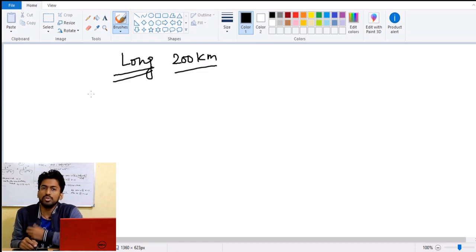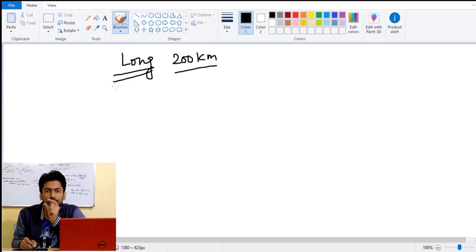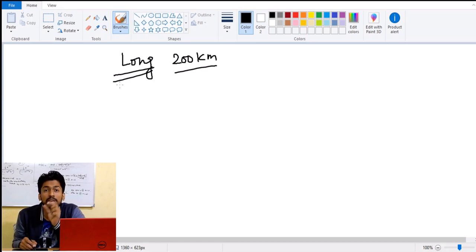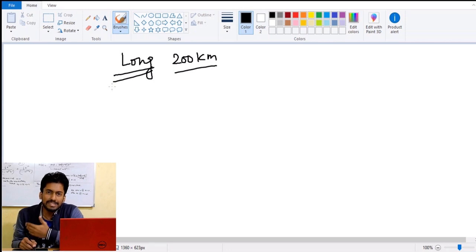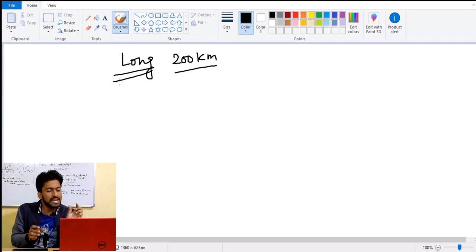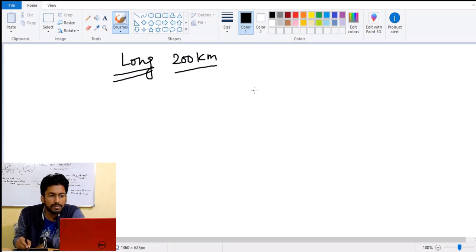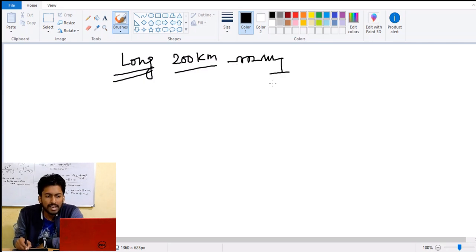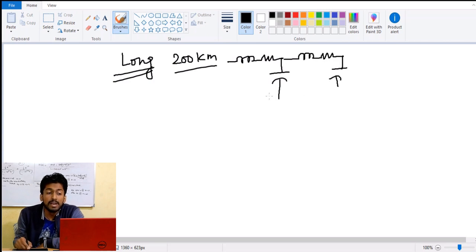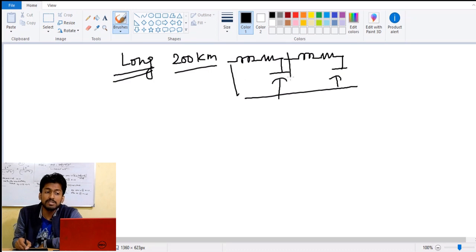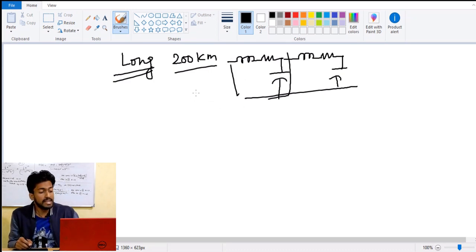In the case of long transmission lines, we cannot analyze the line with the help of lumped parameters. The total resistance and inductance cannot be considered concentrated at a single point. We have to consider distributed parameters — inductance and capacitance are distributed throughout the line, so small sections of inductance, resistance, and capacitance are repeated all along the line.